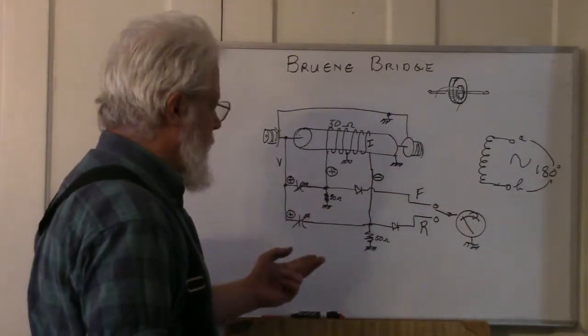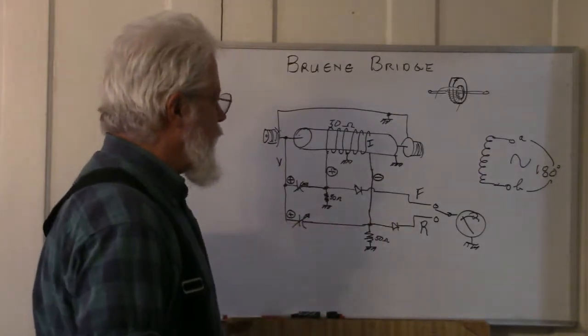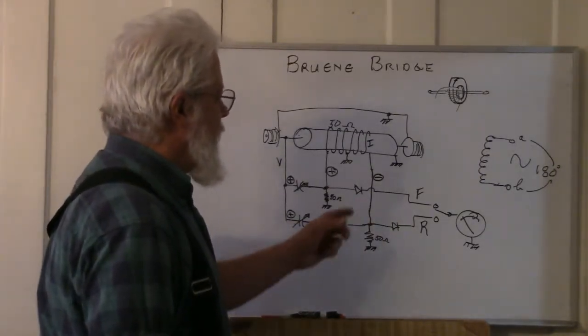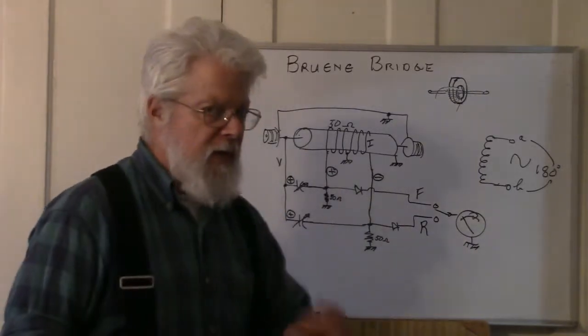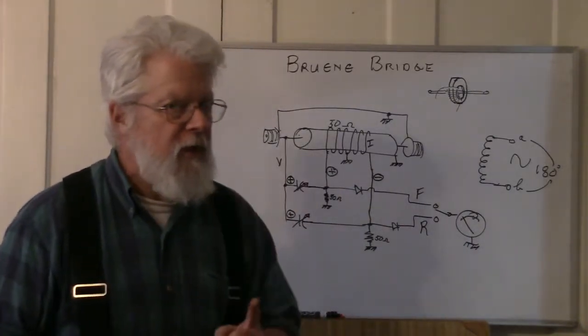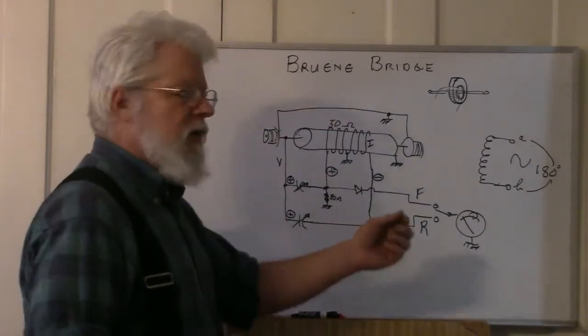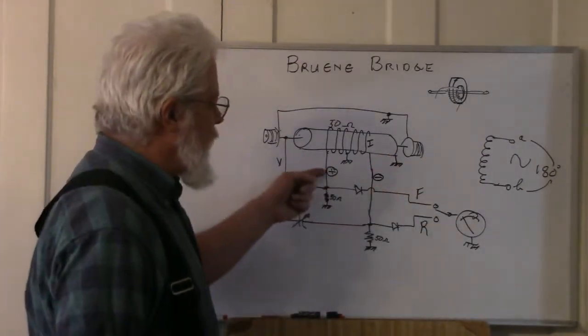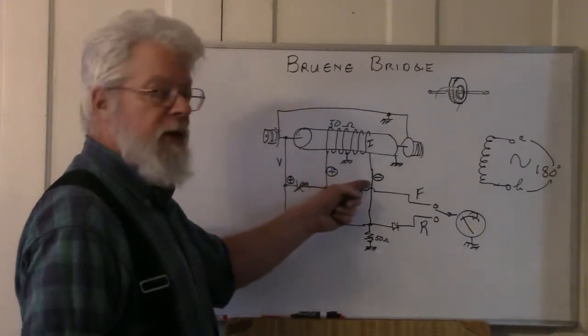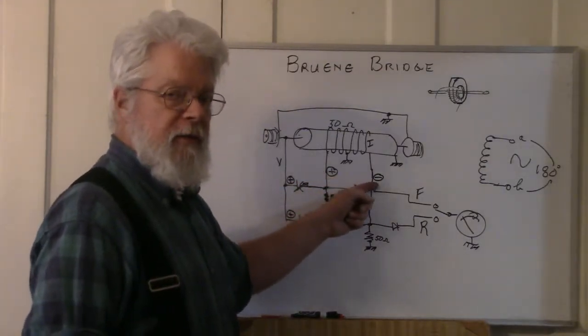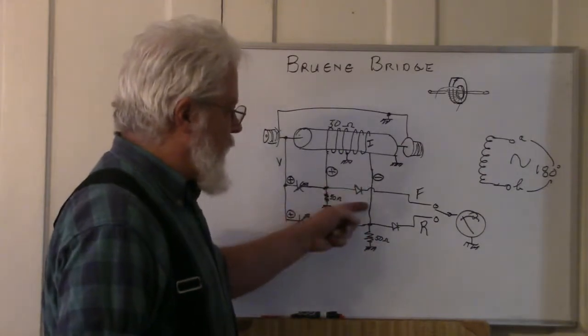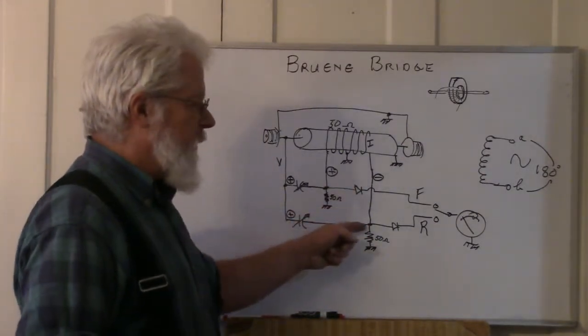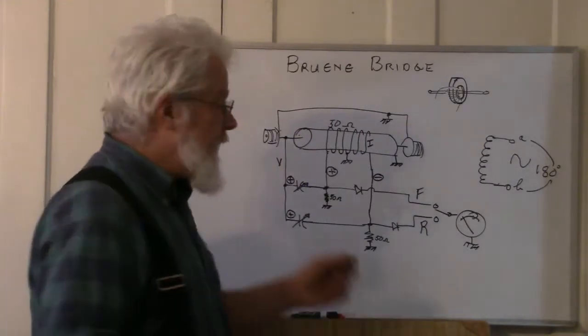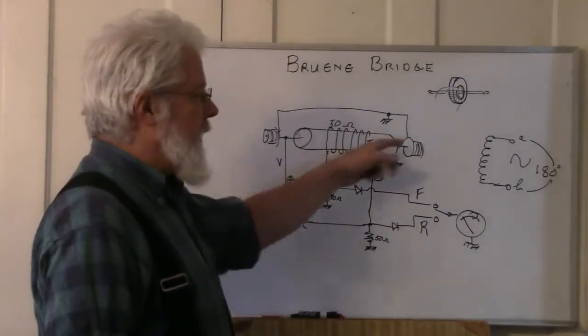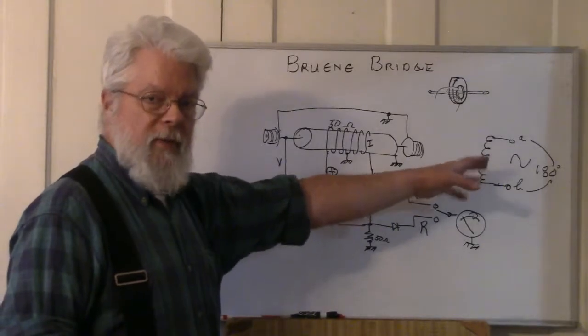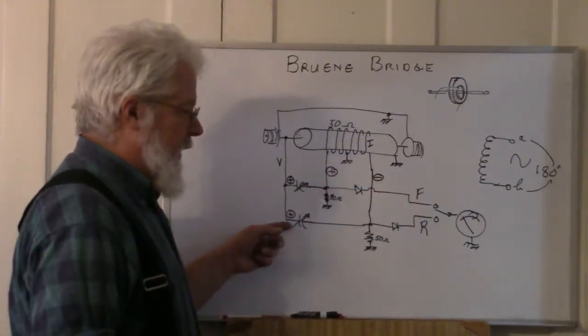When we flip this to the reverse side, we now have the same, not a different, remember, there's only one signal in the line. The signal in the line is the exact same signal we had here, except now it appears here, 180 degrees out of phase. So this voltage and this voltage cancel to zero. And that's how you calibrate this. You terminate this in a perfect load, in a matched load, and you adjust your reflected power for zero.